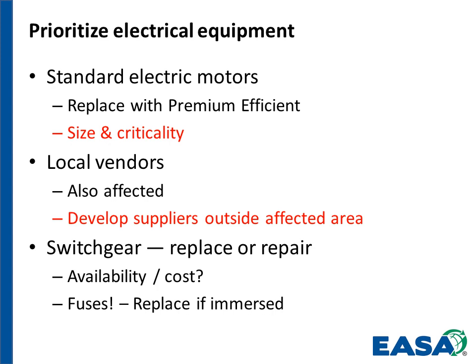But unlike an electric motor, which in many cases is mounted pretty well at ground level because of the way the structure and the piping and so on in the plant is built, a lot of that switchgear could have been permanently installed in a room basically on the second floor or certainly above flood stage.